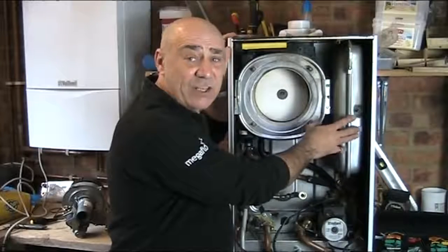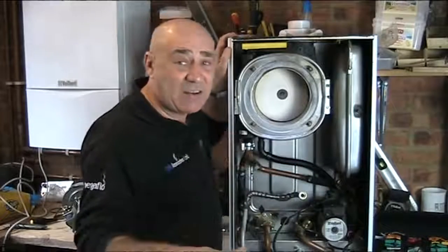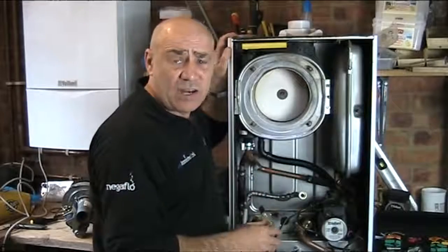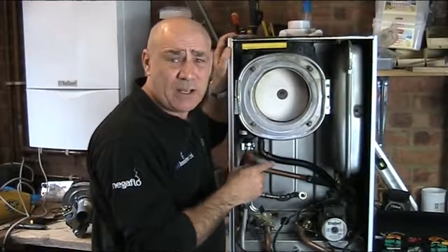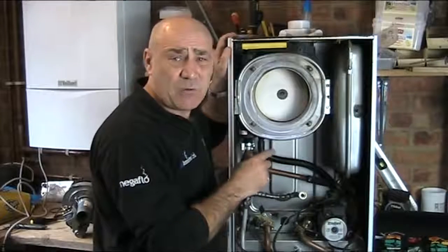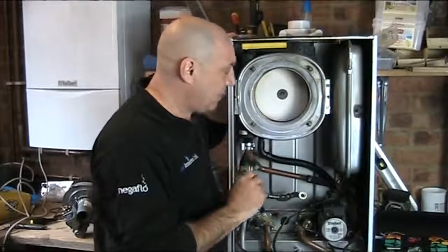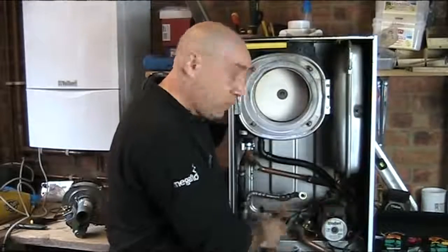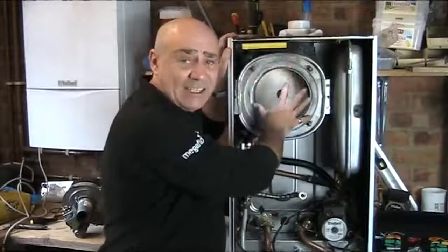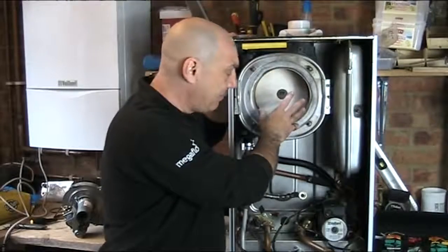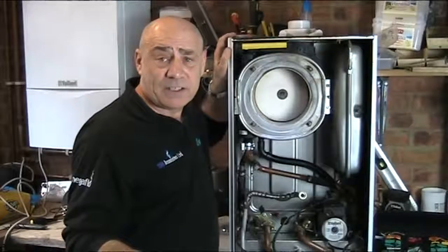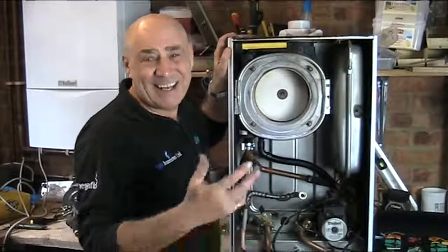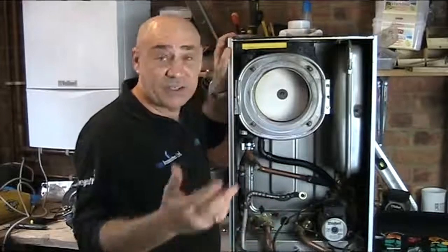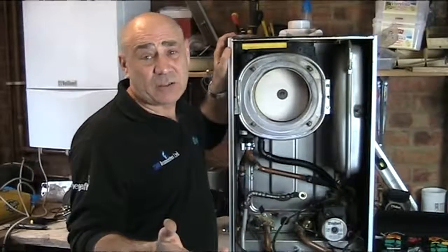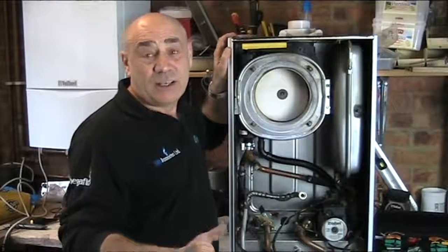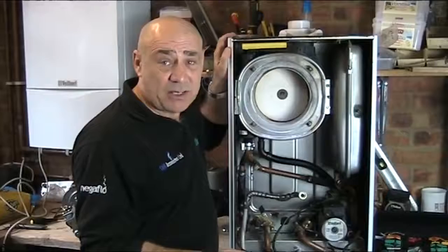But we do this on every single visit, not just a service visit, any kind of visit at all. We check, drain and recharge and set that vessel up properly so you don't get any problems for at least 12-18 months. Very, very important. So, we've done the expansion vessel, the hydro block and the sensor, the heat exchanger, the burner and ignition system, and then we will top up the heating system with chemical as is required if it's starting to get a bit borderline. Or we may just stick some in there anyway, because we use Sentinel X100, which you can't overdose, so it can only be good for the system anyway.